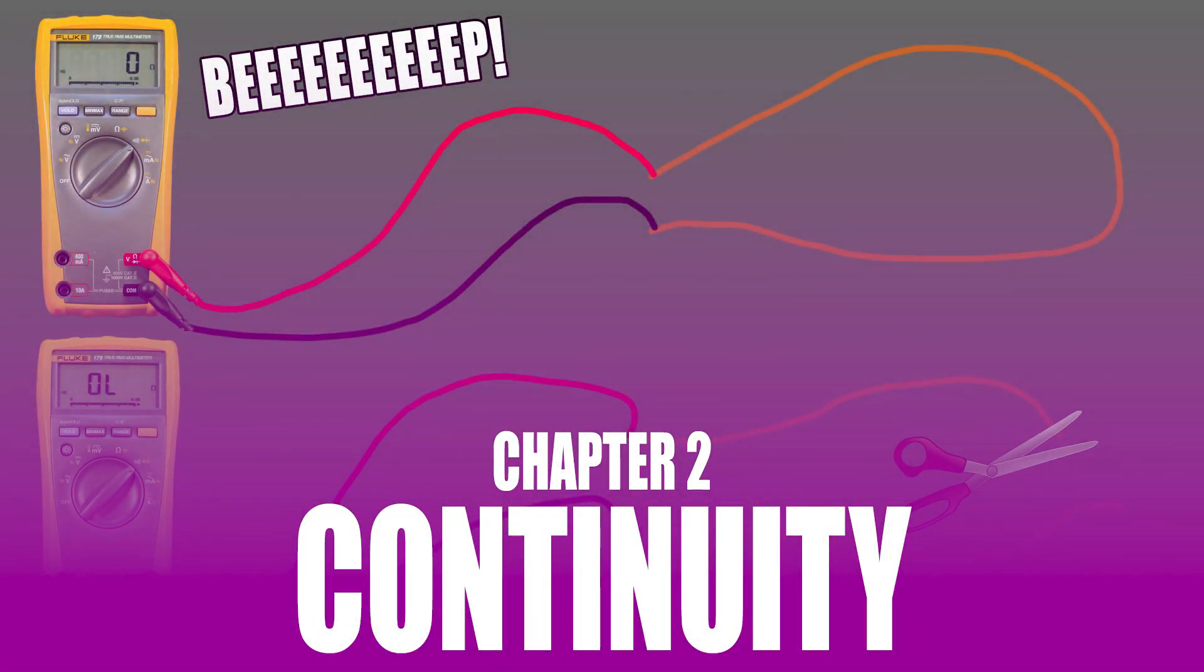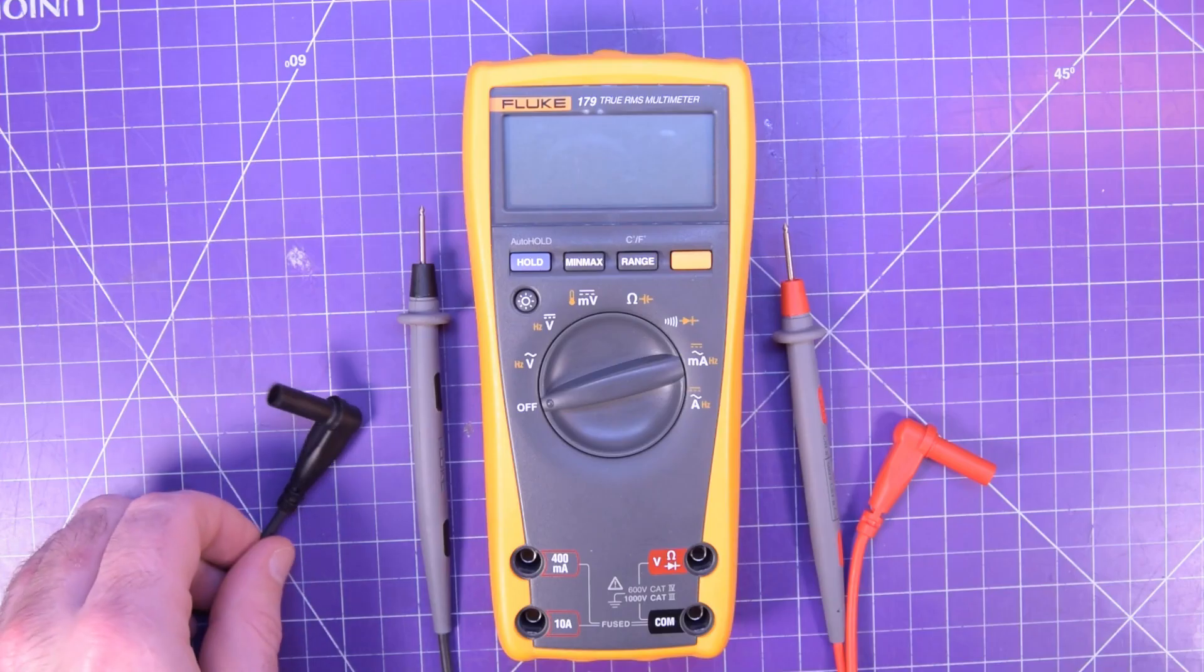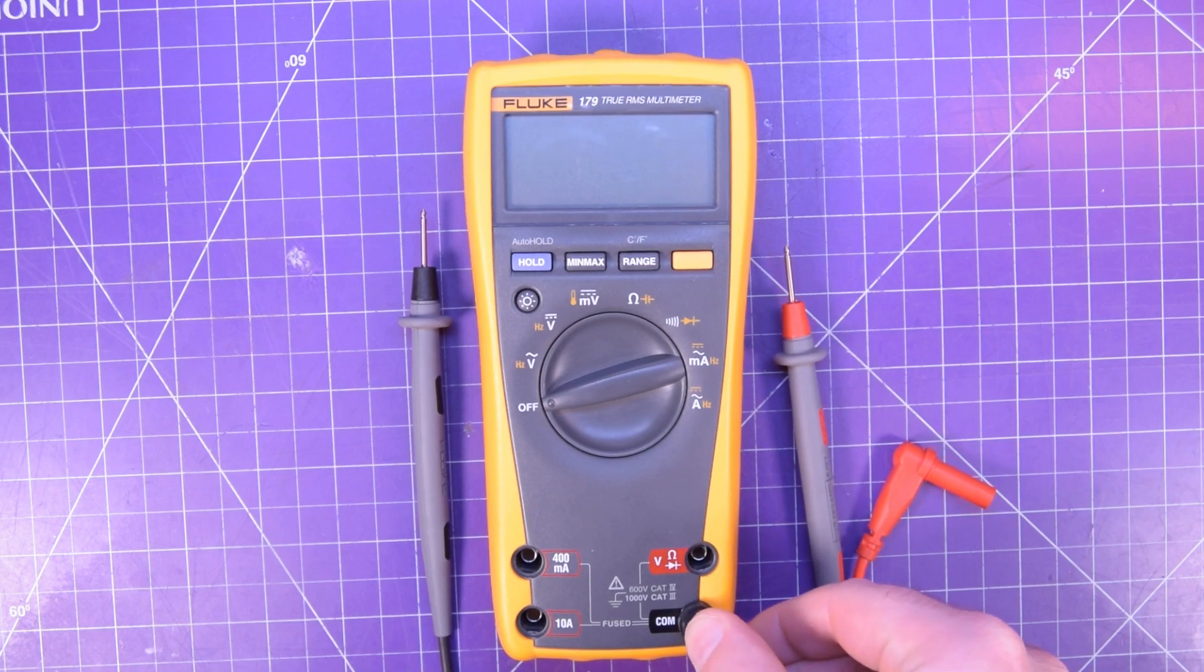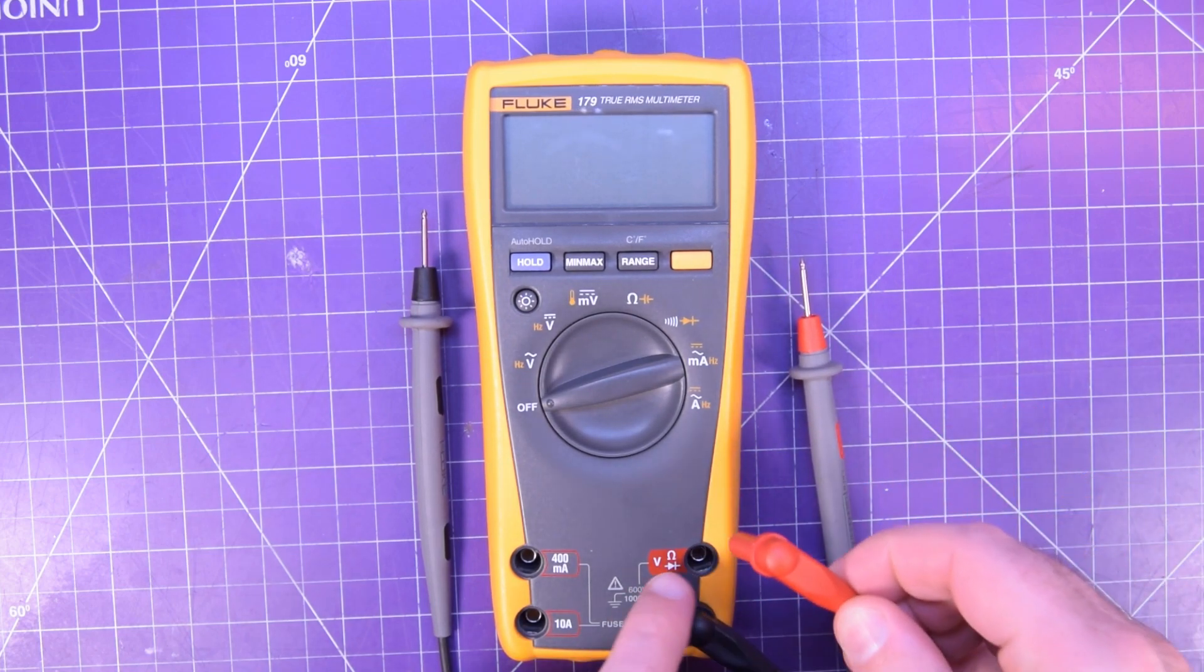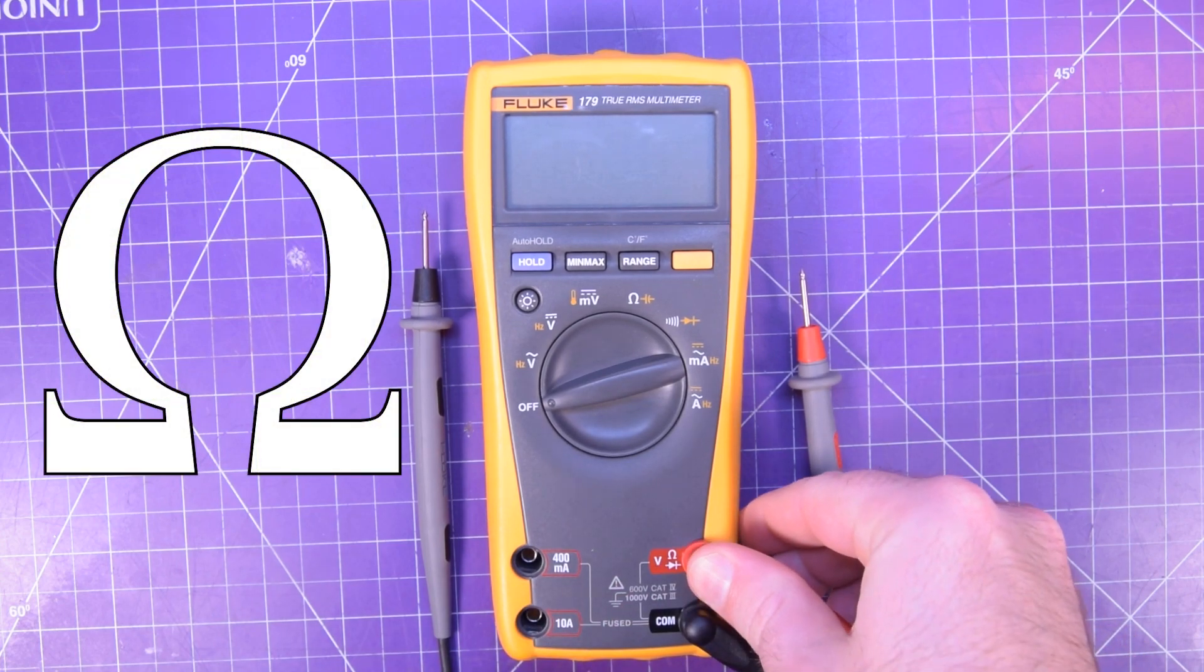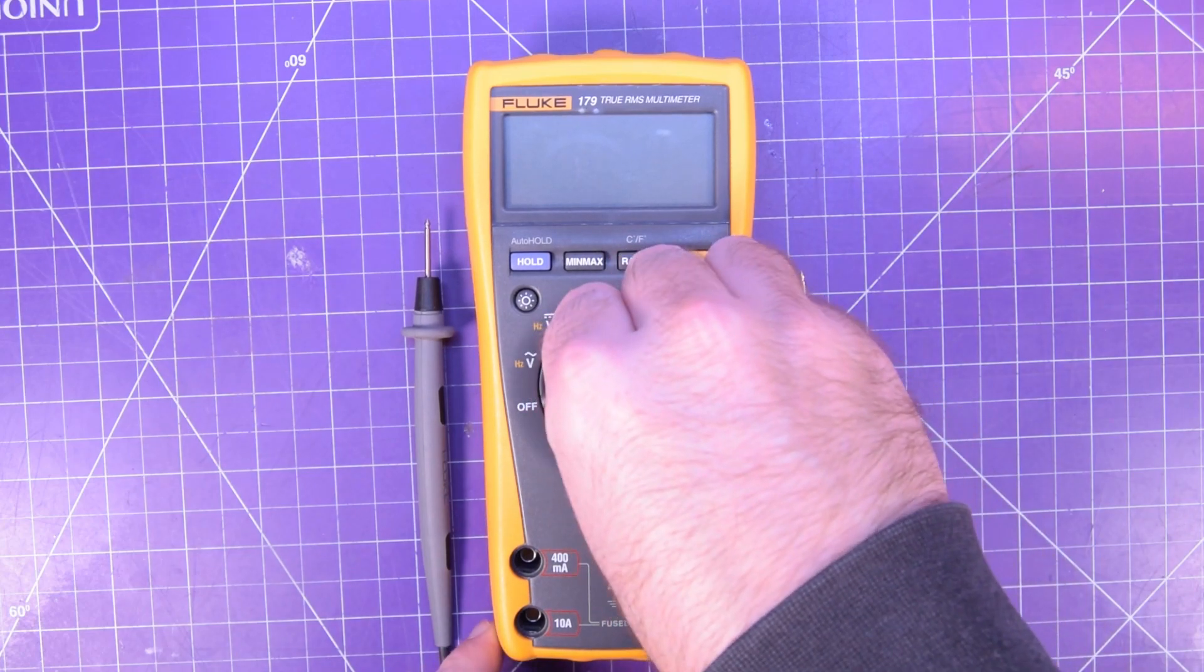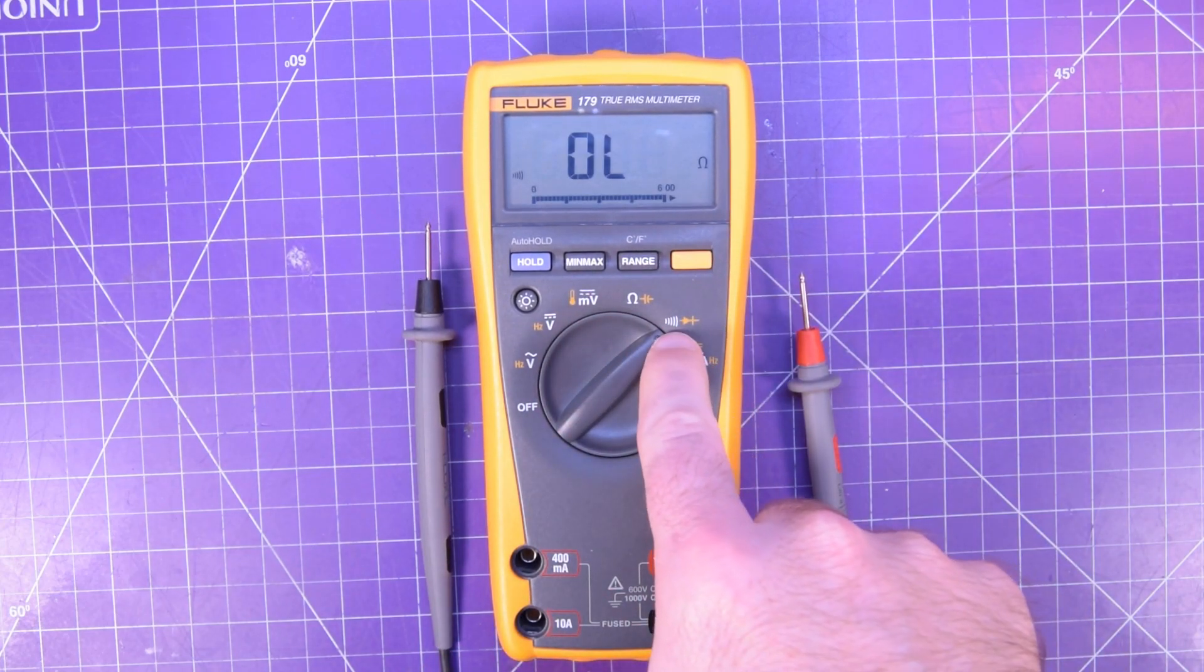One of the most useful functions of a multimeter is the continuity setting. It tells you if a conductor, a circuit, or multiple parts of a circuit are connected to each other. It basically tells you if the conductor you have connected to the red probe is electrically connected to the conductor you have connected to the black probe. First, put your black lead into the black jack labeled COM. Next, put the red lead in the red multifunction jack labeled with the Greek letter omega. Omega is the symbol we use to represent ohms. Then turn the range switch to the continuity function, which looks like a sideways Wi-Fi symbol.